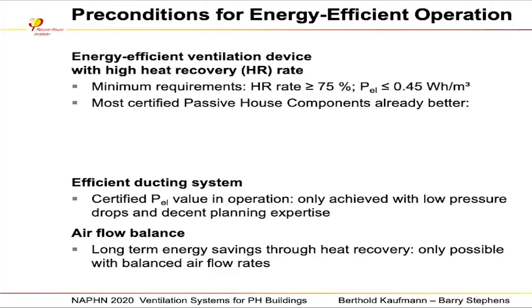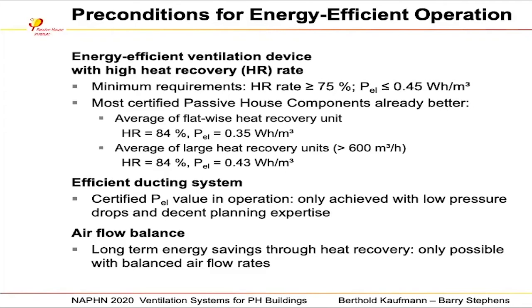Wait, now we have the, please go a step ahead to have all text. You see here, the minimum requirements, heat recovery rate is 75. The electrical requirement is, please have the electrical power not more than 0.45 watt per cubic meter an hour. And what you can see, many systems nowadays have a much better value. We will come later into some more detail what that means and how it is measured.